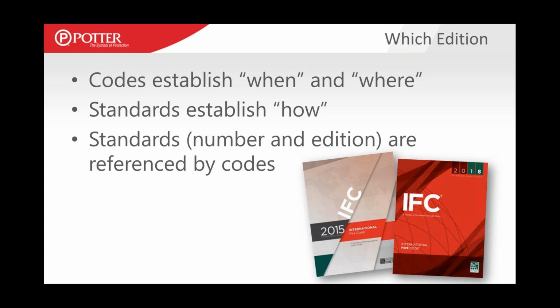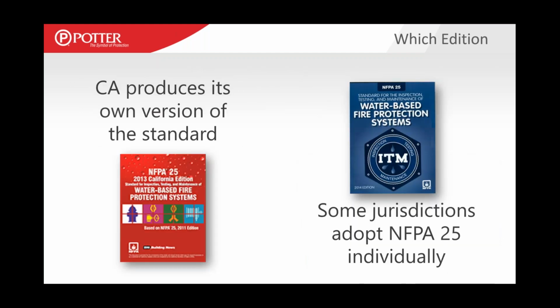Those standards, by reference in the codes, are referenced specifically. So the 2018 IFC here on the slide, for example, references the 2017 edition of NFPA 25. That's typically what happens. The codes adopt the most recent edition that was out when that code was written. So typically that's how it works. Not always, but that's typically how we understand which edition applies where we're at. It's really which edition the fire code, the building code, references. But that's not always the case.